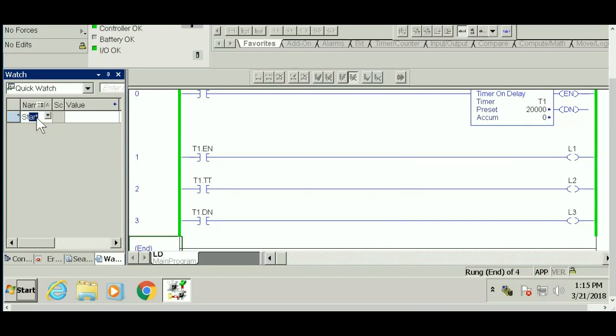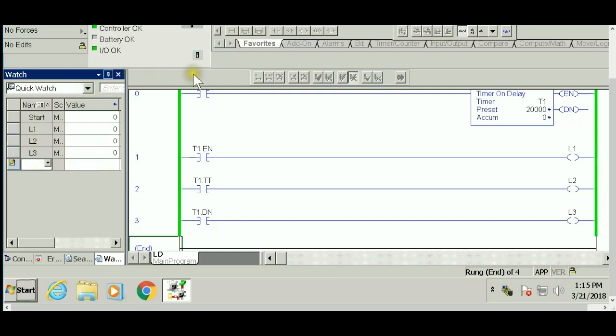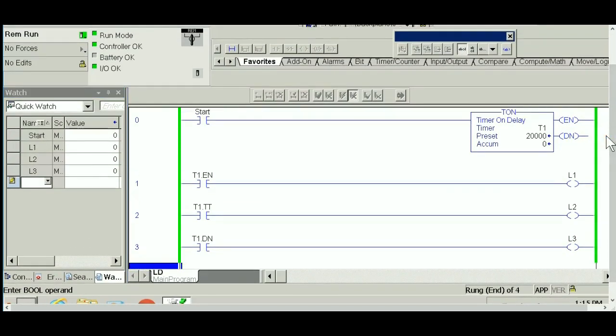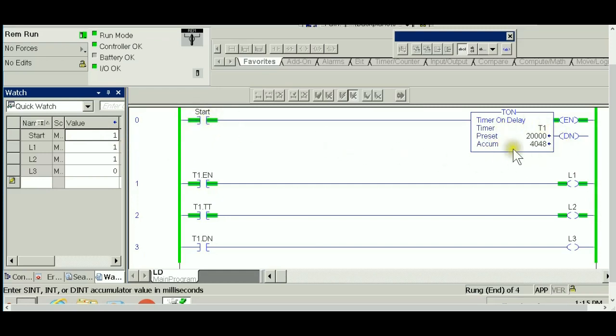In my watch list, I'll have start, light one, light two, and light three. Let's focus on the first rung. As you can see, the XIC referring to start is false because start is a normally open switch reading zero. When I close the switch and it reads one, that's when this instruction is true and the timer is activated.